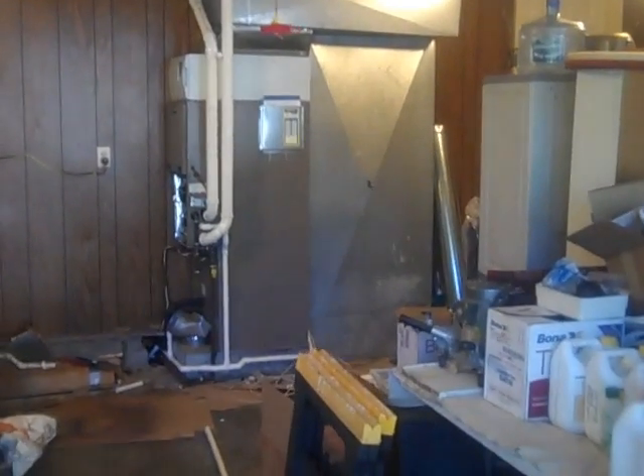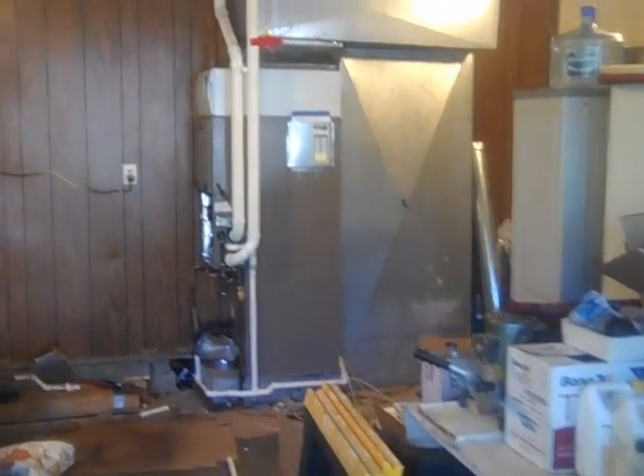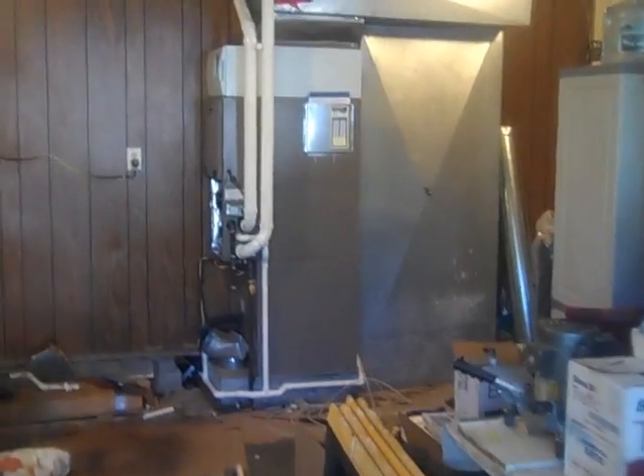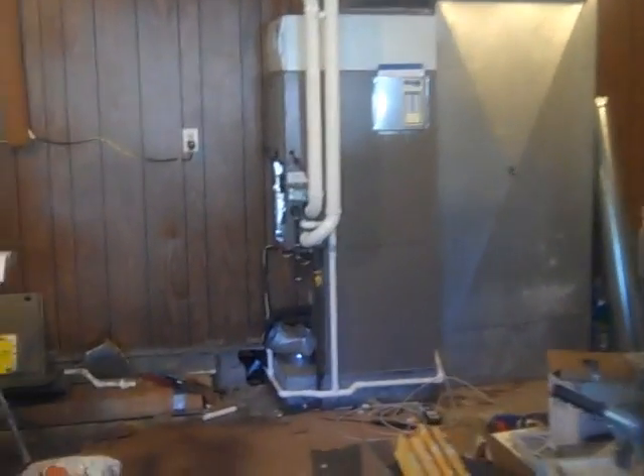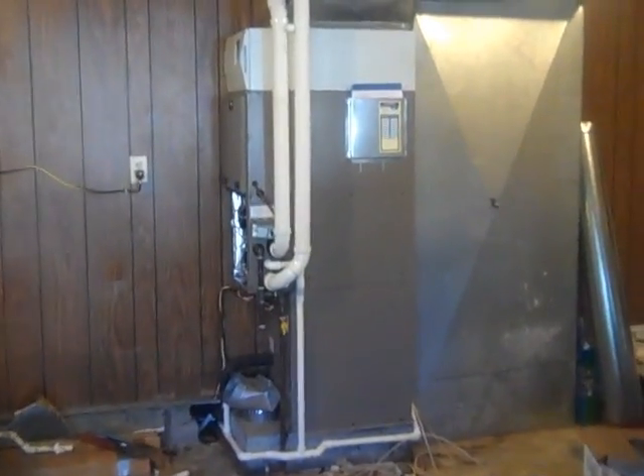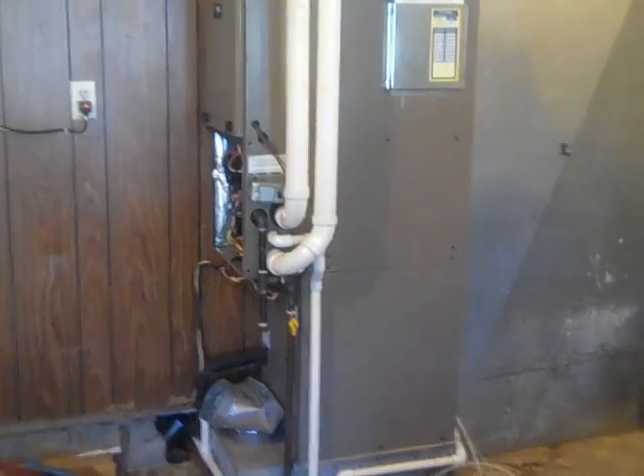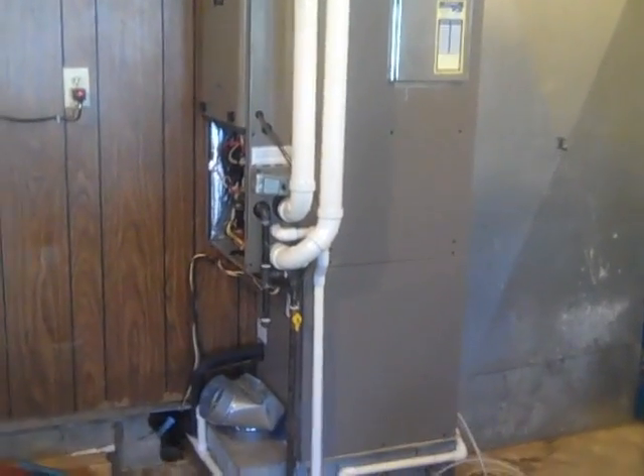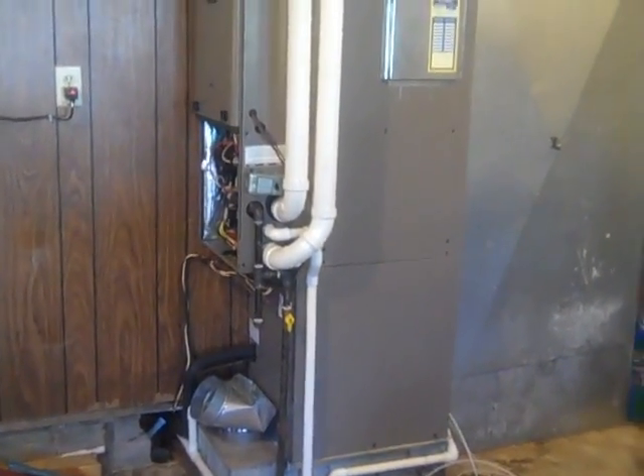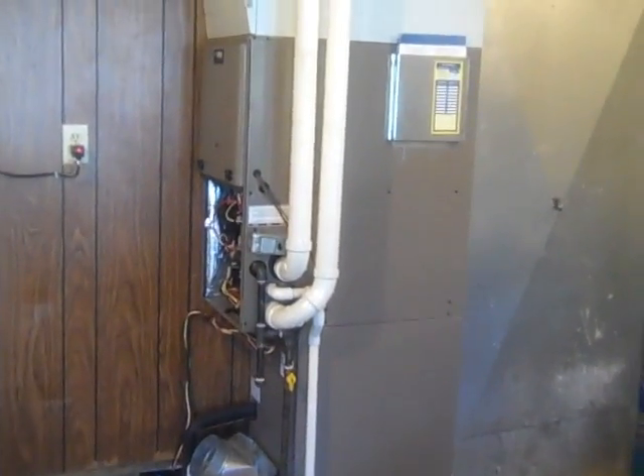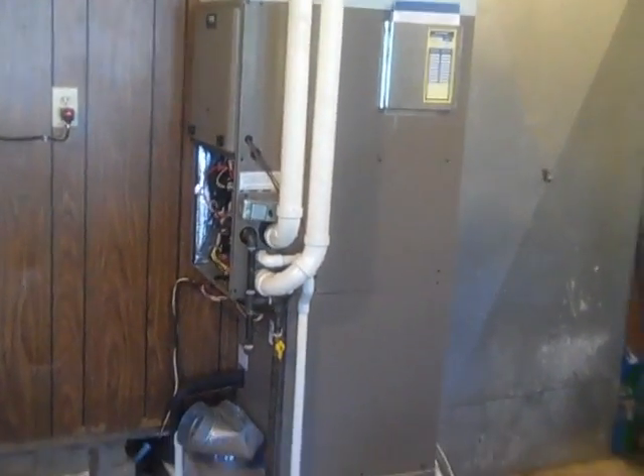Okay, did a changeout here, changed out an 80% Trane. It was 100,000 BTU, now 80,000 out, of course being 80%. This is a York LX 80,000, 95.5% efficient furnace with an X13 motor.